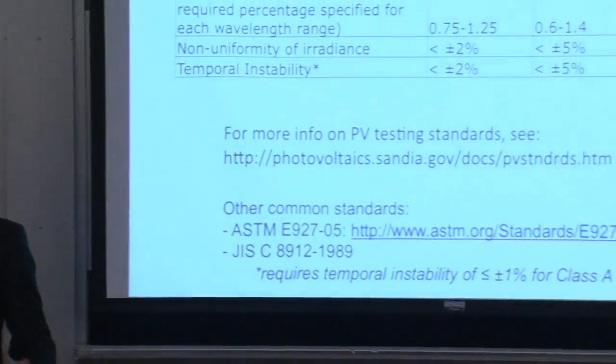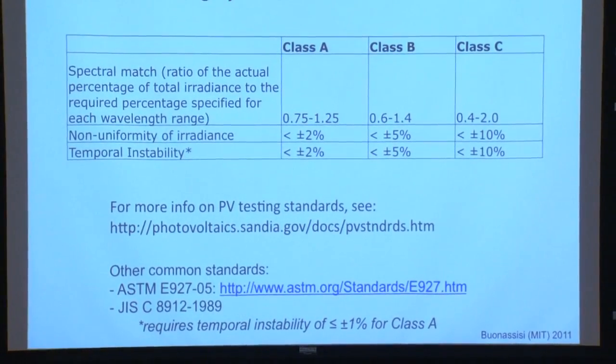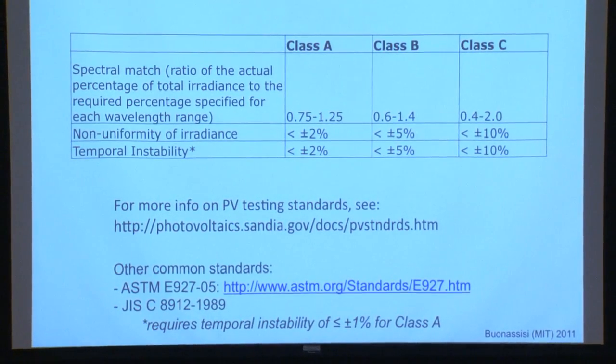Note that the temporal instability for the Japanese standard is a little bit more stringent than the IEC test. Minor detail, but depending on who your collaborators are, where they are in the world, they might be using a different standard than you. Just keep that in mind.